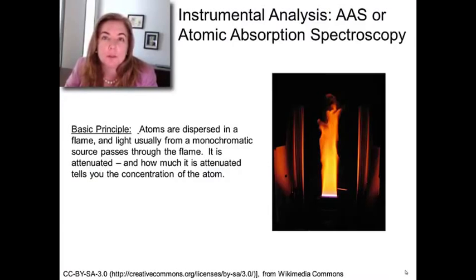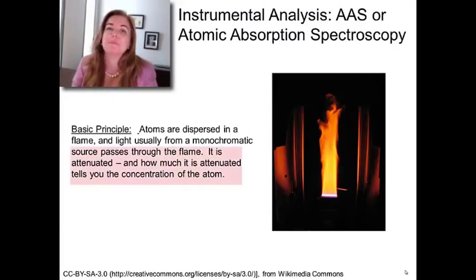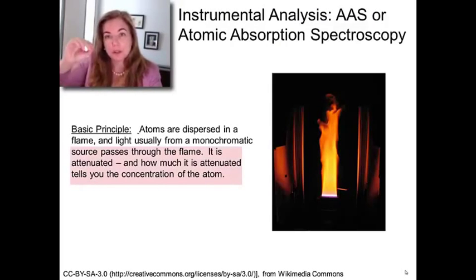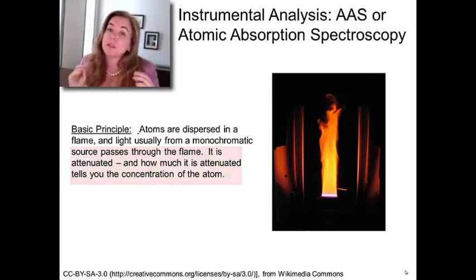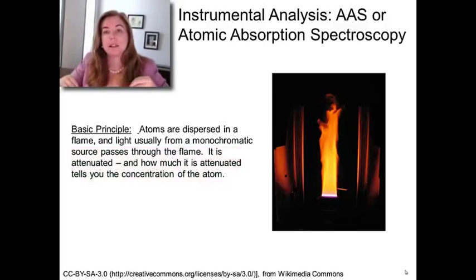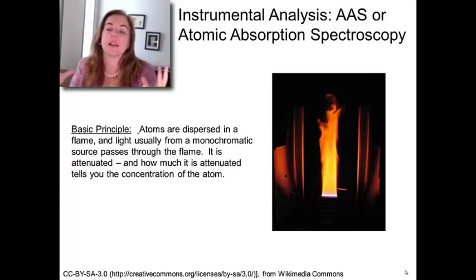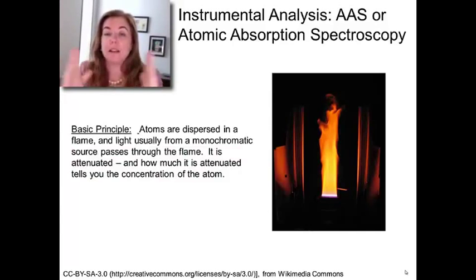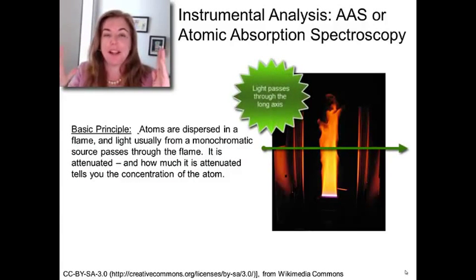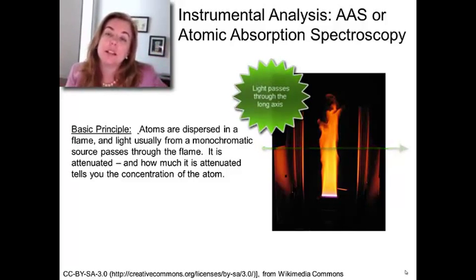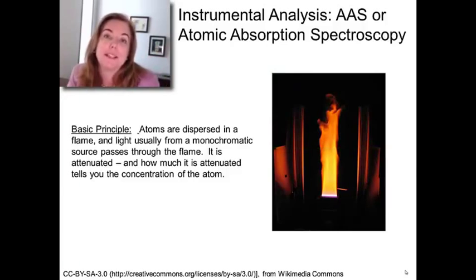We'll be talking about two different techniques: atomic absorption and graphite furnace. In atomic absorption spectroscopy, the simplest way to imagine it is you're taking a liquid sample, pretty clean, sucking it up in a straw, and shooting it into a flame. That flame is hot, and its main purpose is to put the atoms into the gas phase while keeping them in their ground state. You shine light through the long axis of that flame and look at the other end to see what is missing, what the flame absorbed, and from that you deduce the elements that are present.